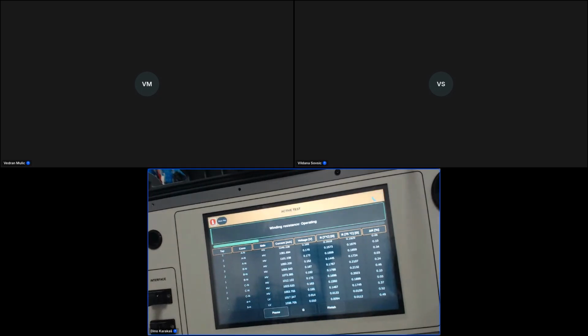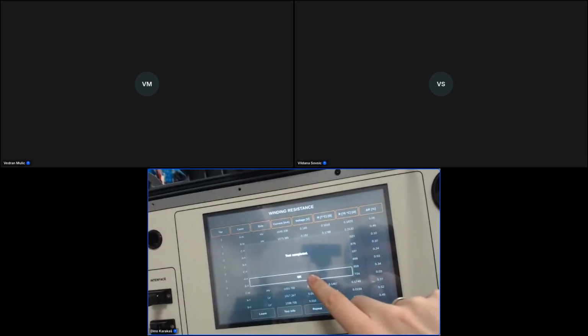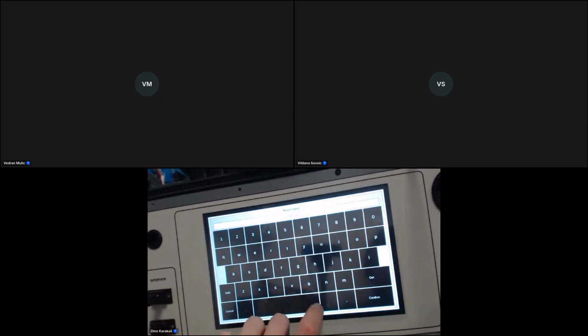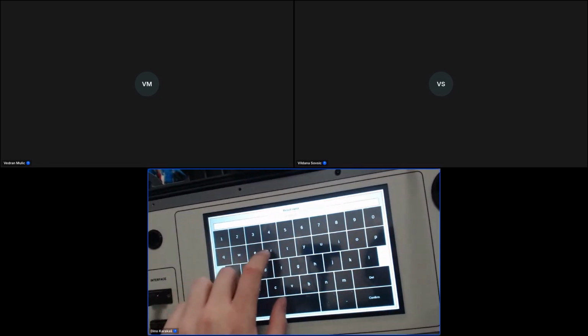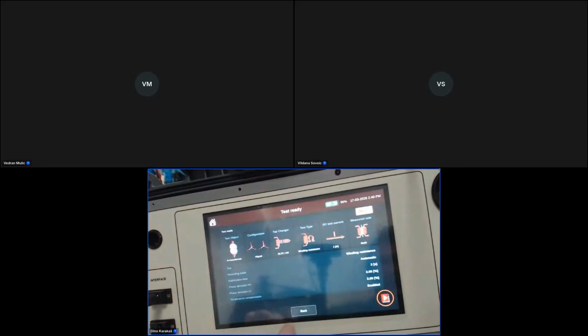And we have phase C on the low voltage side. It was quick. Okay, the test is completed. Press OK, and we can save these results. Again, we will give it a name, webinar, winding resistance. We confirm and we leave it.